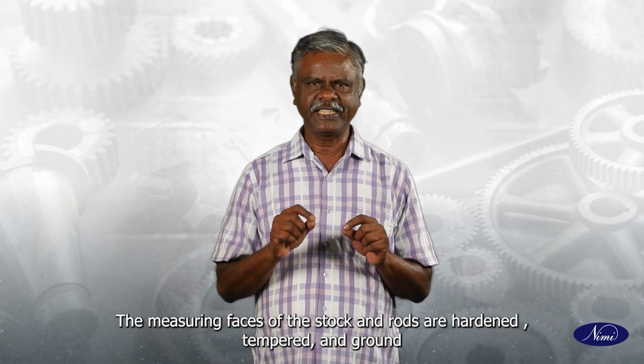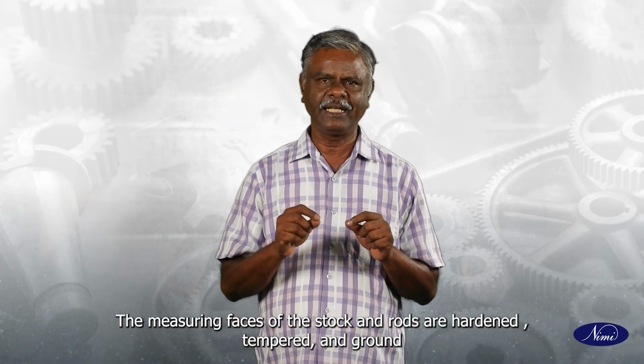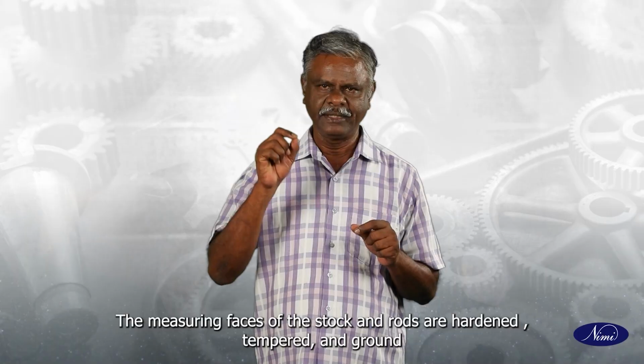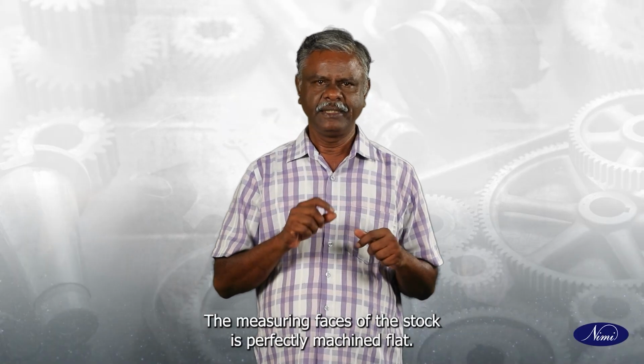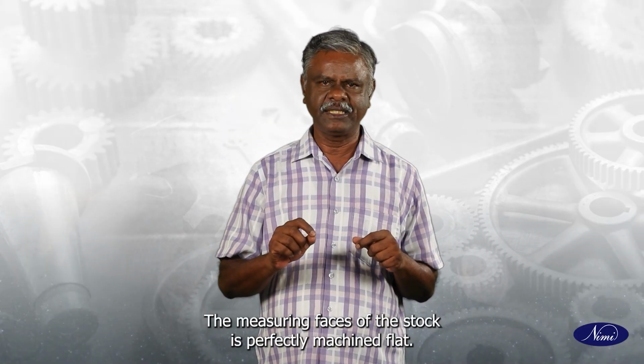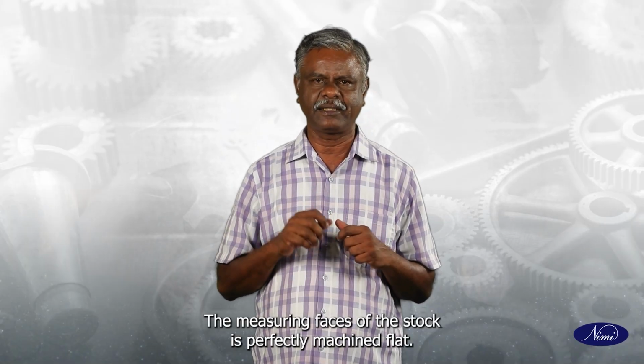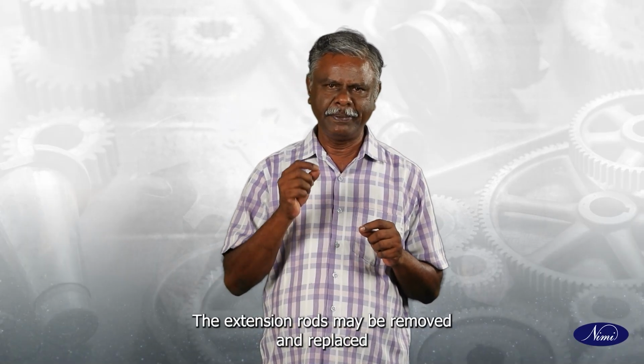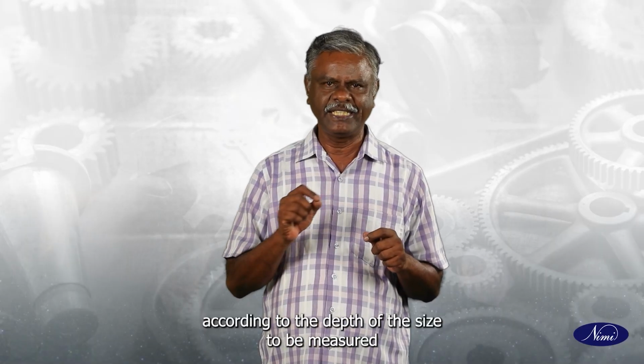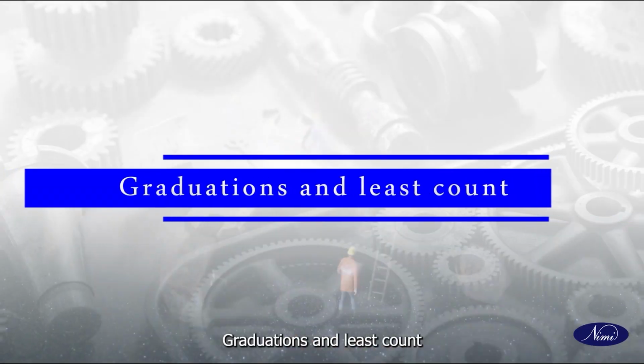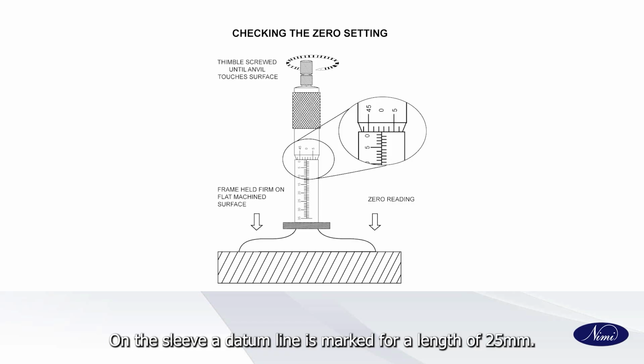The measuring faces of the stock and the rods are hardened, tempered and ground. The measuring faces of the stock is perfectly machined flat. The extension rods may be removed and replaced according to the depth of the size to be measured. Graduations and least count. On the sleeve, a datum line is marked for a length of 25 mm.